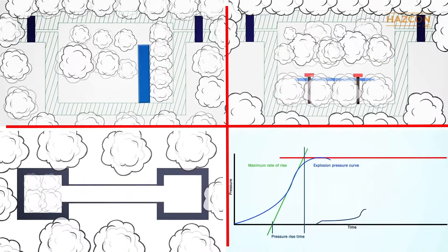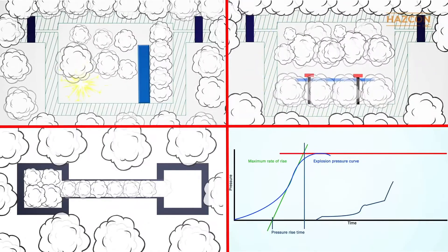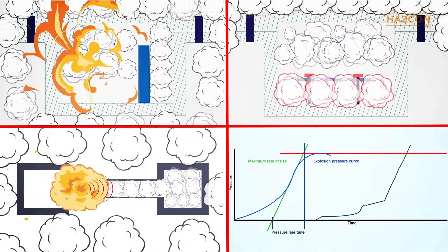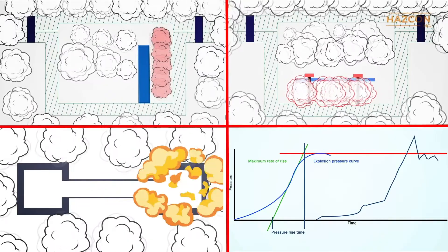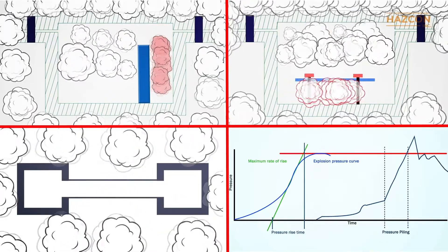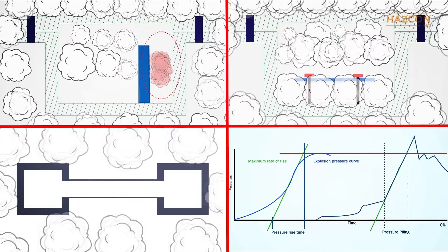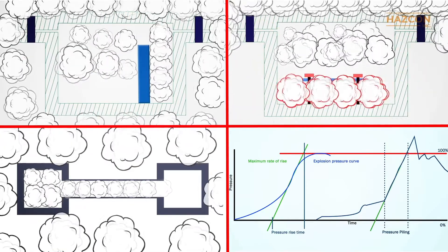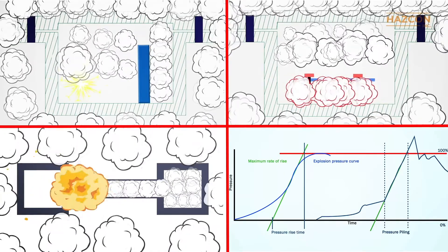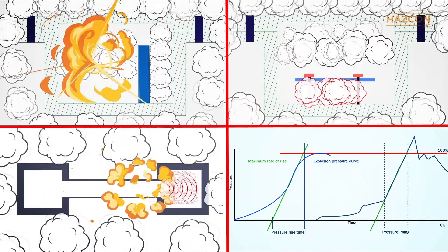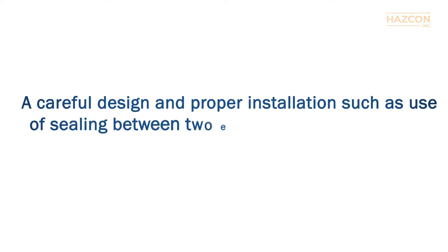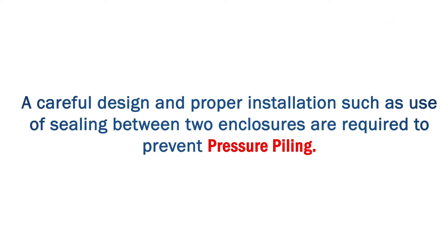In summary, we should remember that pressure piling results when gases become highly pressurized through compression, and when unburned gas pushed into a cavity becomes highly pressurized before being ignited. As a result, pressure piling leads to pressure that is higher than the expected peak pressure as a result of an explosion. Given such increased pressure, enclosures and piping systems might be unable to withstand the impact of an explosion. A careful design and proper installation, such as use of sealing between two enclosures, are required to prevent pressure piling.